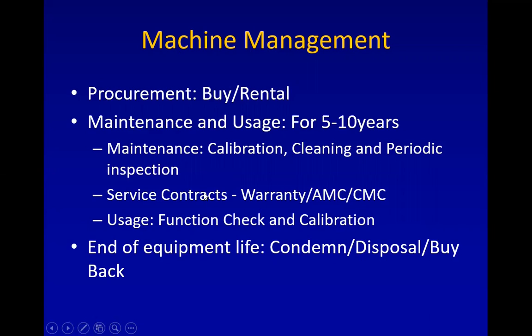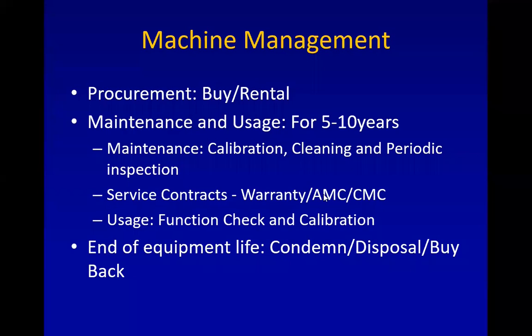There are various types of service contracts. Initially, the equipment is under warranty, so any repair work is done by the service provider free of cost, and any defective part is replaced free of cost by the manufacturer. The second type is the annual maintenance contract (AMC), which does not cover damaged parts — the service provider charges for the part replaced but not for the service. In a comprehensive maintenance contract (CMC), both service and parts are replaced free of cost. AMC and CMC are usually done on an annual basis.